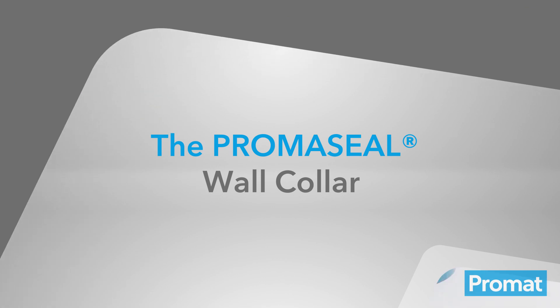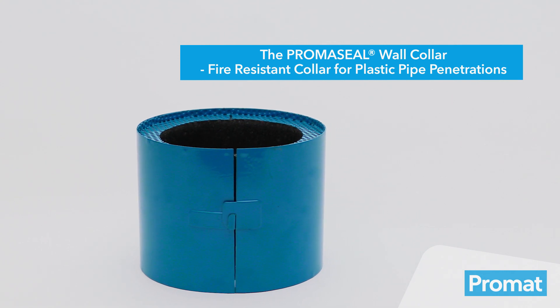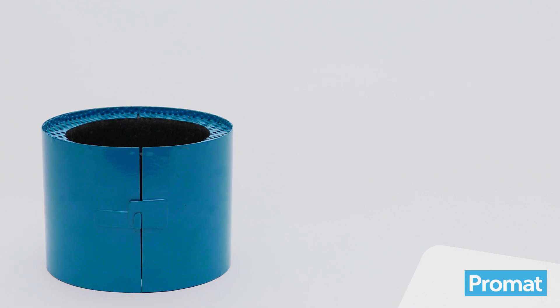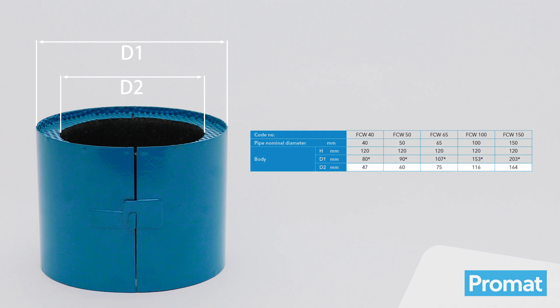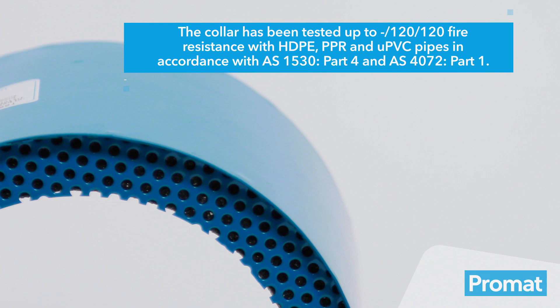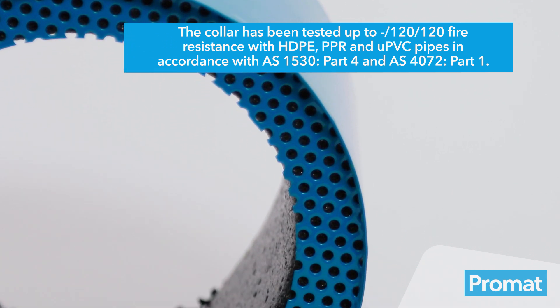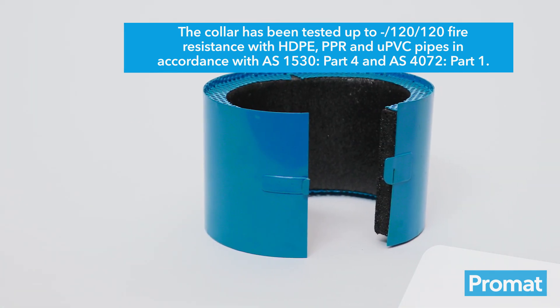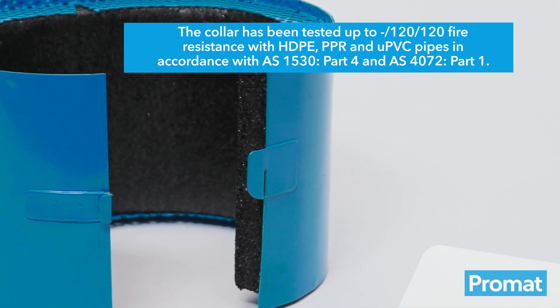The PROMASEAL wall collar is designed for insertion into wall elements made of plasterboard, concrete or masonry. It is a split type collar for retrofit installations to lightweight or masonry walls, to suit plastic pipes up to 162 millimetres outside diameter. The collar has been tested up to -/120/120 fire resistance with HDPE, PPR and UPVC pipes in accordance with AS1530 Part 4 and AS4072 Part 1.